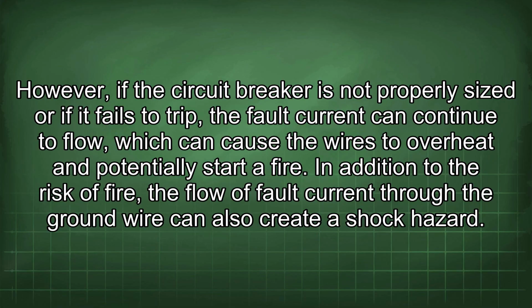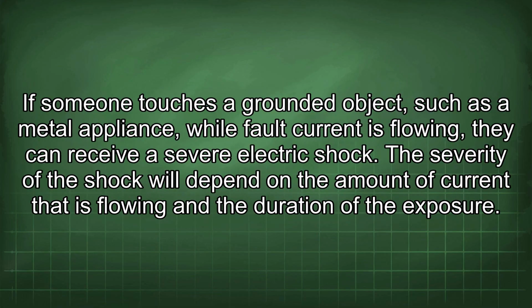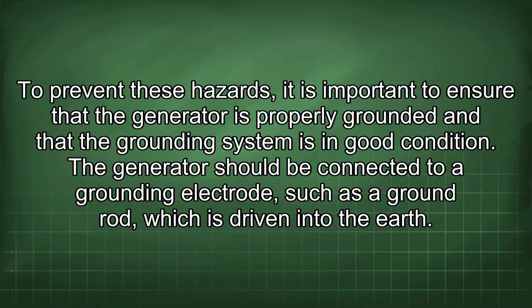In addition to the risk of fire, the flow of fault current through the ground wire can also create a shock hazard. If someone touches a grounded object, such as a metal appliance, while fault current is flowing, they can receive a severe electric shock. The severity of the shock will depend on the amount of current that is flowing and the duration of the exposure. To prevent these hazards, it is important to ensure that the generator is properly grounded and that the grounding system is in good condition.